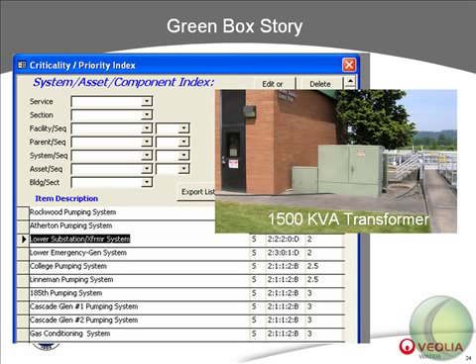So, what is so special about this substation? Well, during the workshop group discussions, it became clear that this substation was a single power feed to the old or northernmost plant. This portion of the plant is much lower and receives about 5 million gallons of sewage per day by gravity. Without power to this lower side of the facility, the treatment process would fail, and the potential was that 5 million gallons per day would go to the Columbia River.